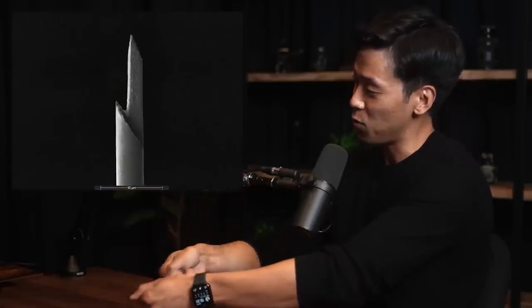This is the needle that's engaging with the loops in the thread. They're the ones that thread the loop, and then peel it from the silicon backing, and then this is the thing that gets inserted into the tissue, and then this pulls out, leaving the thread. And this notch, or the shark tooth as we used to call it, is the thing that actually grasps the loop, and it's designed in such a way that when you pull out, it leaves the loop. And the robot is controlling this needle.